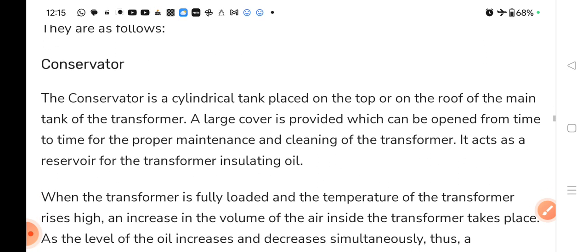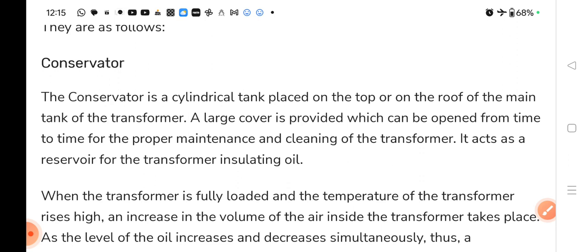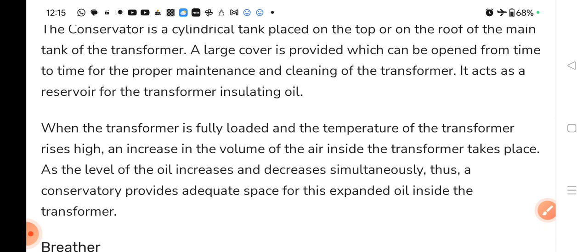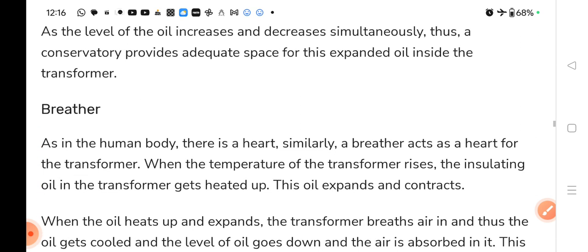उसके अंदर हम insulating oil रखते हैं ताकि transformer में oil की कमी न हो. When the transformer is fully loaded and the temperature rises high, there is an increase in the volume of oil inside the transformer. As the level of oil increases and decreases simultaneously, the conservator provides adequate space for this expanding oil. Temperature बढ़ने से oil expand या decrease हो सकता है, तो उस time पे conservator काम आता है क्योंकि वहाँ पे already adequate space बना के रखा है expanded oil के लिए.